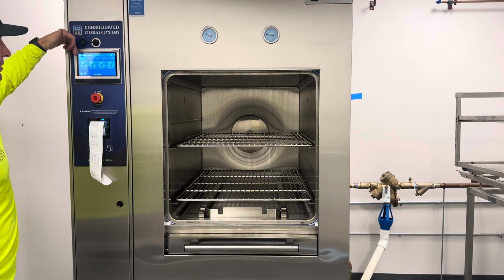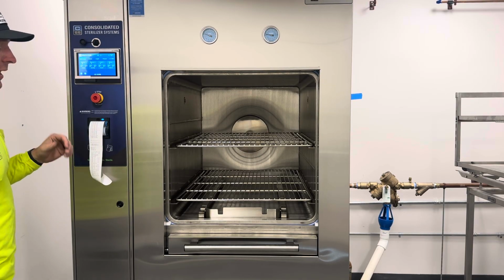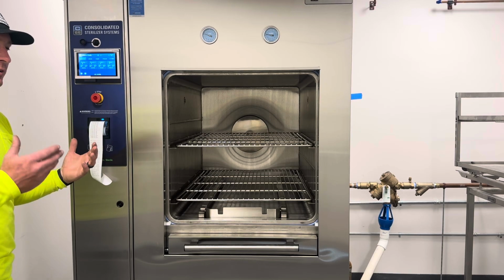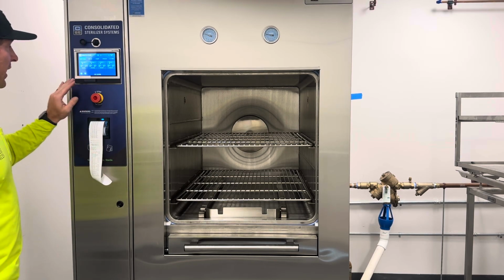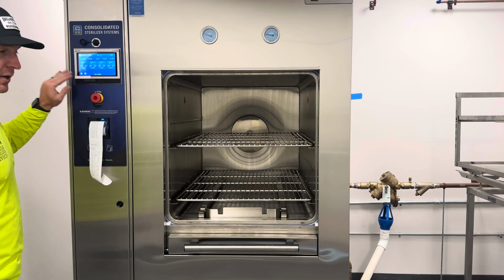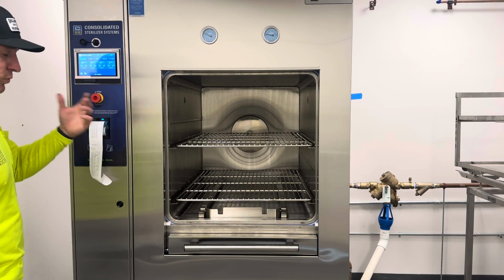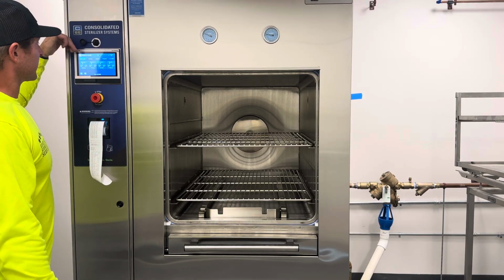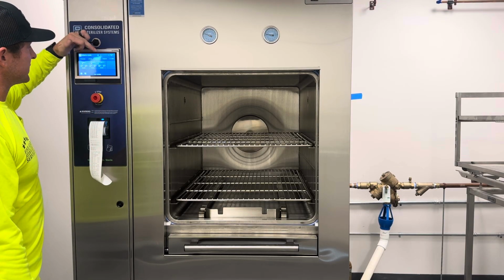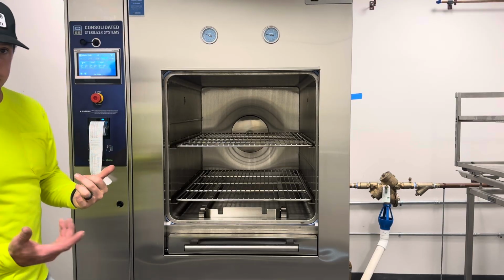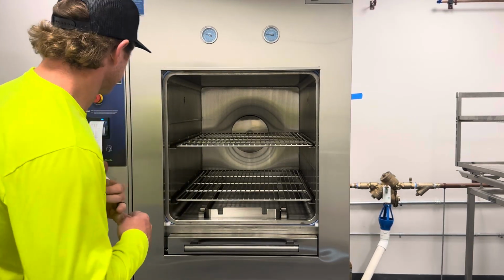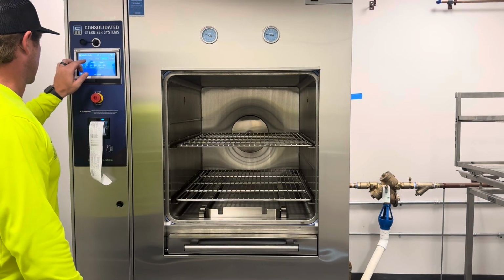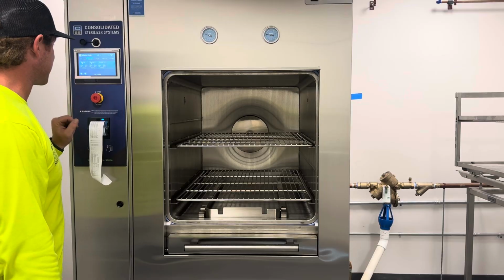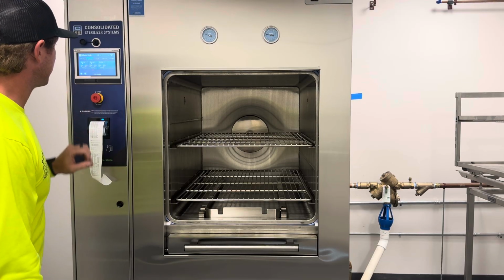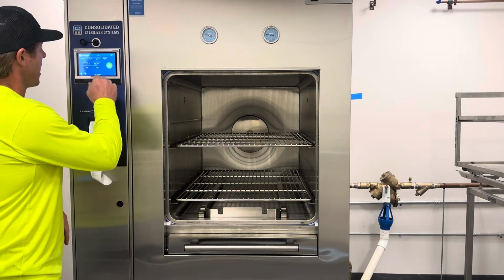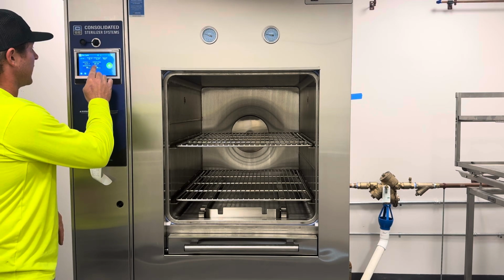We have favorites, which you can pre-program, and most people only run 3 to 4 cycles maximum, and you can input those cycles right here on the favorites, so they're always just ready to go when you are. However, you have the option to press the gravity tab, liquid tab, or vacuum tab if you so choose to run one of those types of cycles. Okay, so just for demonstration purposes, I'm going to click a gravity cycle. I'm going to alter my parameters, which you can do right here on the touch screen. So we're going to alter a gravity cycle.